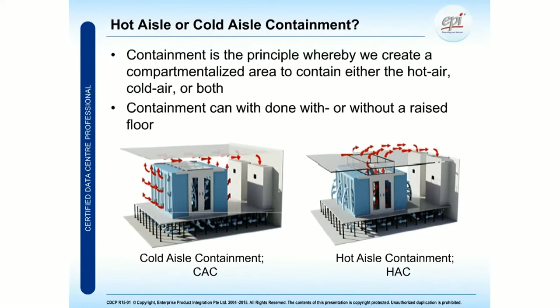This will improve your efficiency a lot. Now, it does not necessarily have a big difference whether you are going to apply a hot aisle contained area or a cold aisle contained area, as long as the cold and the hot airflow keep separated as much as possible. And this will create your high efficiency.